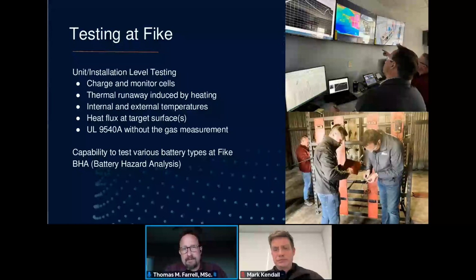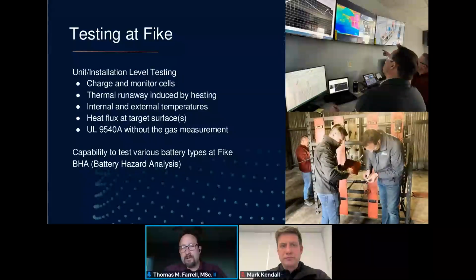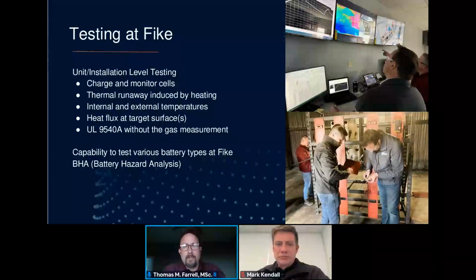And you can see our labs in some of these pictures here. We're monitoring temperatures in various locations inside of the pack, outside of the pack, and heat flux on target surfaces around, both in accordance with guidance in UL 9540A and also in some other places that we know to be strategically important for a client, whether that is sensitive equipment nearby, or battery to battery spacing to help them optimize their spacing as well. Basically, we're doing a UL 9540A test without gas measurement.